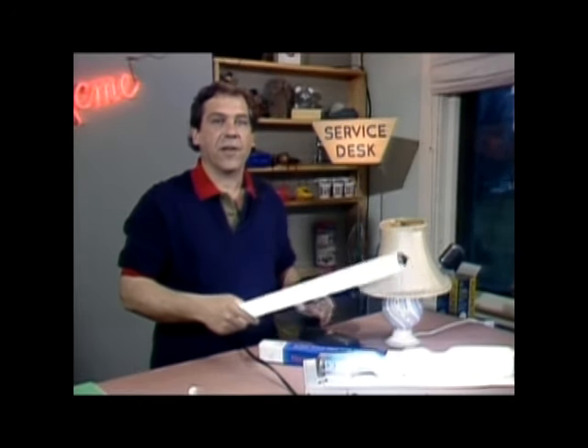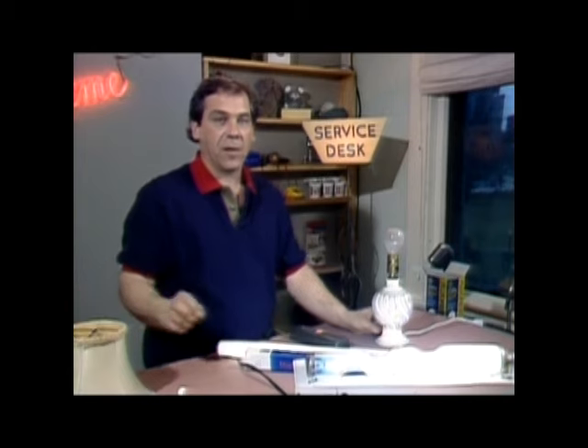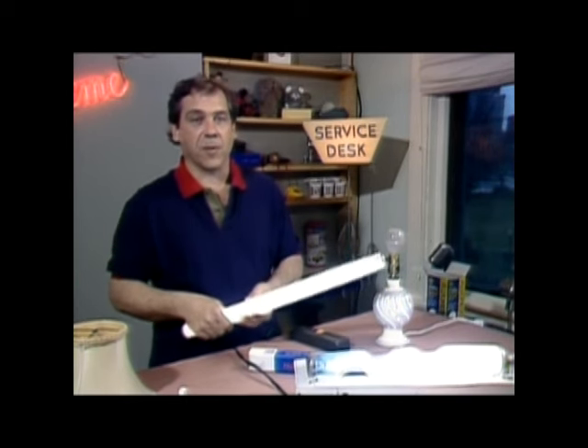The fluorescent light is a very efficient way to create light from electricity. Incandescent light works by heating a metal to the point where it gives off light. The direct excitation of atoms results in a light with very little heat. And those are the two reasons that fluorescents are always used in large buildings — the direct conversion to light saves on light per watt, and the absence of heat saves on air conditioning. The unit used to measure emitted light is the lumen. A 40-watt fluorescent lamp produces more than 70 lumens per watt, while a 40-watt incandescent only gets up about 12.